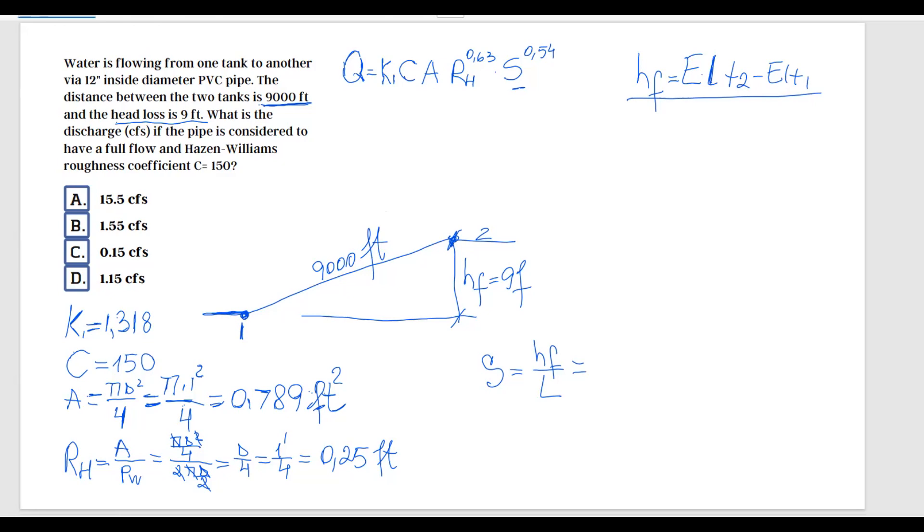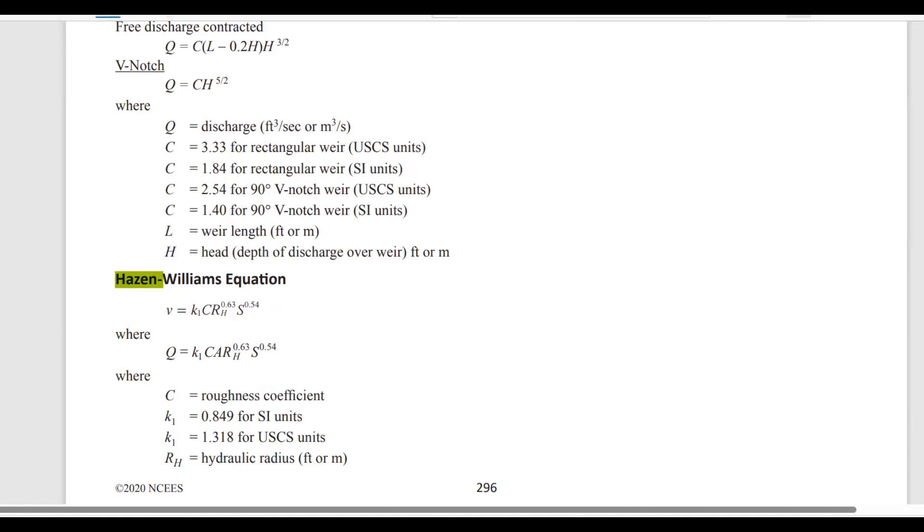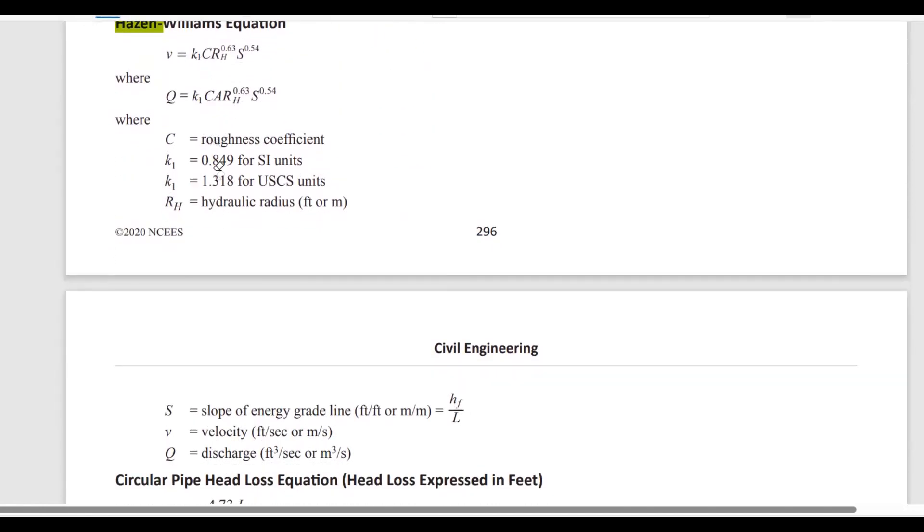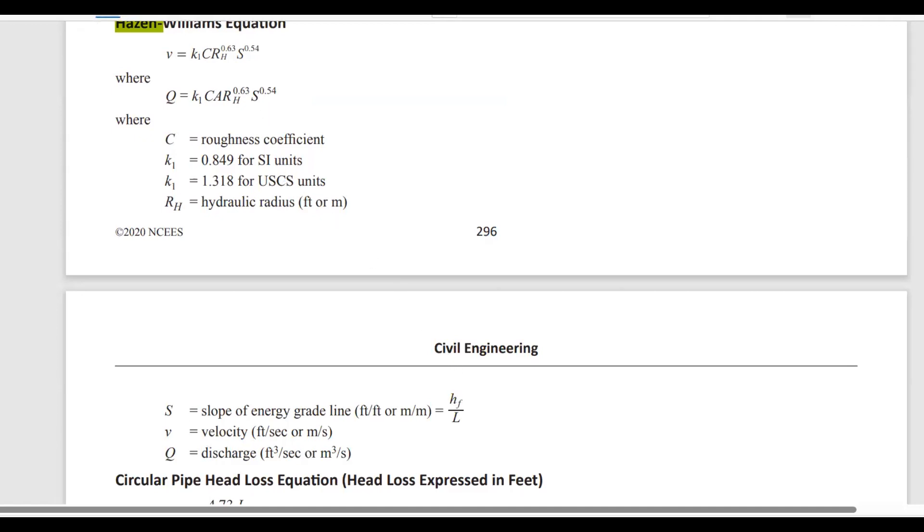Interestingly enough, this formula actually is given in the FE handbook. Let's go back to the FE handbook. Let's say you don't know how you can use the head loss and the length to solve the problem. Here, right after the Hazen-Williams equation, you're told that the slope is the head loss—which is the static head loss, the difference in elevation—divided by the distance between the two tanks. So now that we know that, we can come back here and I'm going to substitute: 9 feet divided by 9,000 feet, which equals 0.001.